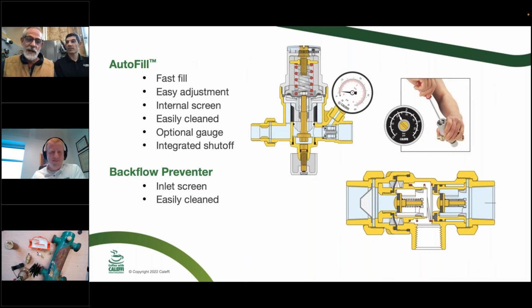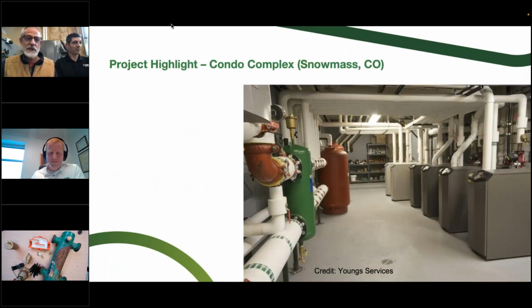Also in that job right there, notice you can't quite see them, but there are variable speed pumps on the distribution just out of the picture there. And those boilers also have variable speed pumps on them. So the flow through that hydro separator is always changing, depending on what the load is. One boiler's on, two boilers on, they're up to high fire, they're low fire. The distribution pump is only going to a couple condos. So that's the beauty of a hydraulic separator, where your two flow rates on your boiler side and your distribution are constantly changing by quite a bit from one side to the other.